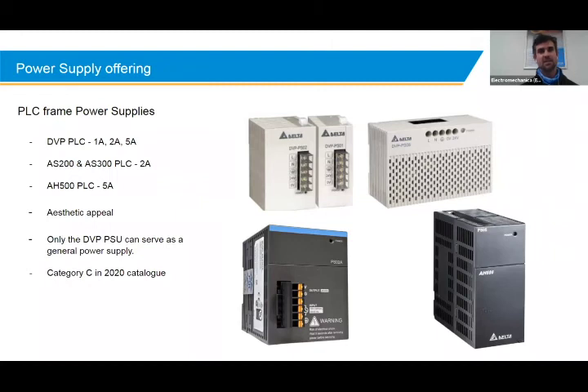Last but not least, in terms of the power supplies, is our specific PLC type power supplies. So the DVP power supplies, the ones at the top here for our DVP range PLCs, are actually one of the most popular in the catalog, believe it or not. People do like these type even when they're not using a PLC. We saw quite a lot of the 2 amps in particular. So yeah, these power supplies are mainly for PLC systems when you want to keep the aesthetics the same. If you've got a DVP frame, it looks nice with the DVP power supply, and the same with the AS PLC, and the same with the AH500 PLC.